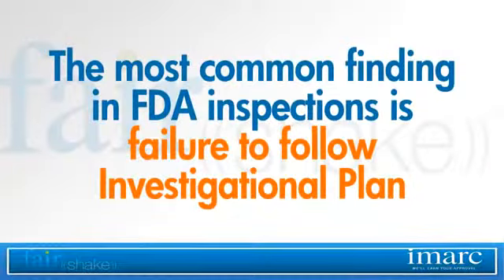And in the investigational plan, we need to know what's in that investigational plan. The most commonly cited finding in FDA inspections to date, still every year, is failure to comply with the investigational plan.